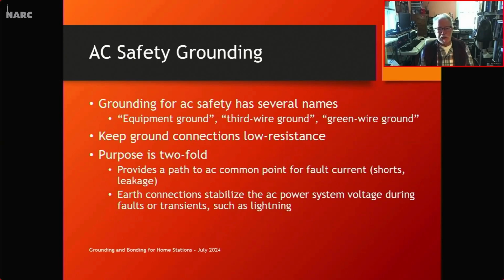The other thing that these connections do is stabilize the AC power system voltage. There's thousands and thousands of these earthing connectors on power poles and at your service entry and all kinds of other places like substations. And none of them are particularly good, and certainly one of them is not enough. But when you have thousands of these in parallel, it stabilizes the AC power system voltage during faults and transients, such as lightning, or perhaps there's an auto accident and knocks the lines into each other and that kind of thing. It helps the entire system from going to really high voltages, so it's a stability thing.